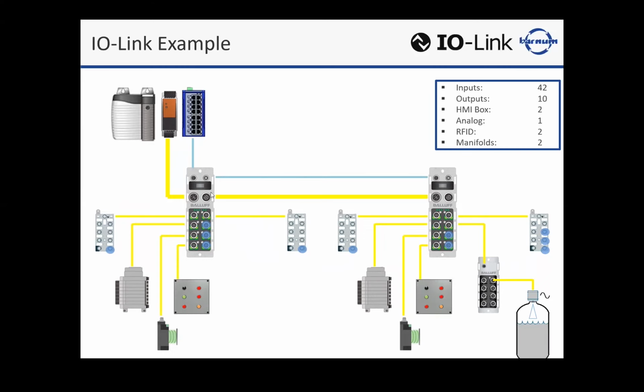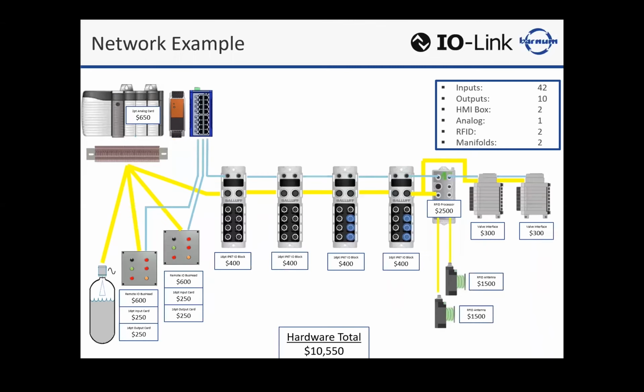Also aux power. You see we daisy chain aux power from master to master. But John, if you take a look back at the network graphic, notice how most of these devices, we have to daisy chain aux power to each device. Oh, yeah. With the advent of electronics today, most of those devices are very low current consumption, so it doesn't need the 8 amps coming out on that 7/8 mini connector. But here, we have to daisy chain that to keep the integrity of our power drop. So that gets very, very expensive. In the IO-Link model, we're basically just connecting our aux power to our masters. So there's a great reduction in standard media costs, both network and aux power.